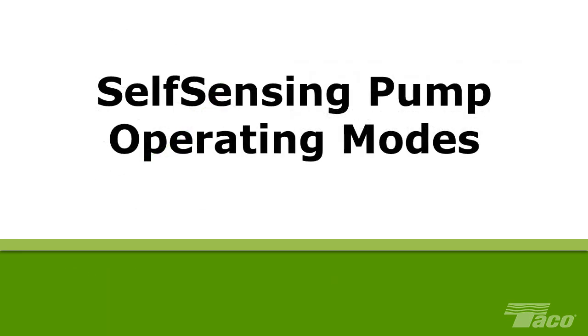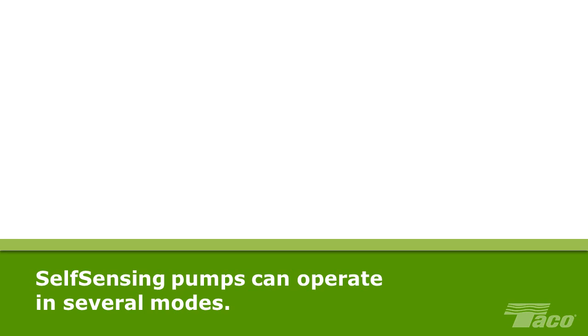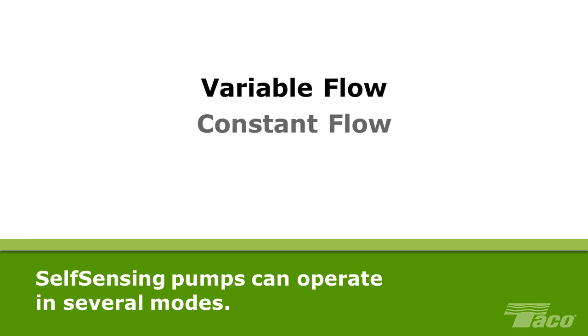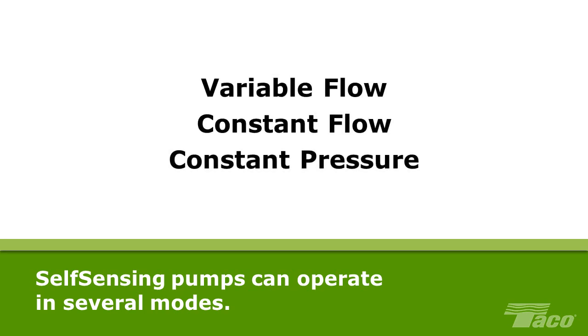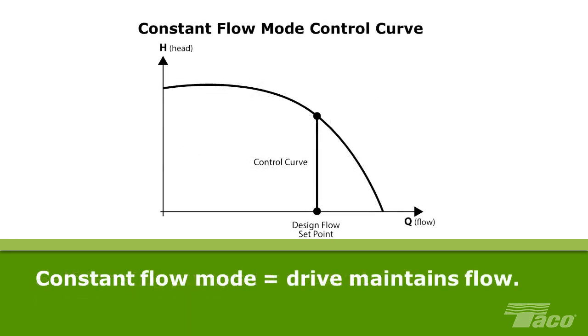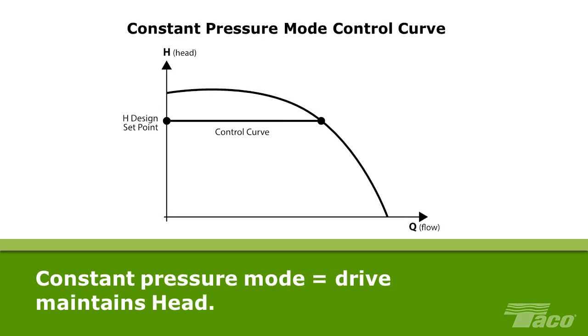Self-sensing pump operating modes. The Taco self-sensing pump can operate in one of several modes based on the shape of the control curve. In constant flow mode in the primary loop, for example, the drive will maintain the desired flow regardless of system resistance. The constant flow target is indicated by a vertical control curve. The drive will maintain constant pressure in similar fashion. The horizontal control curve indicates the drive is operating in constant pressure mode.